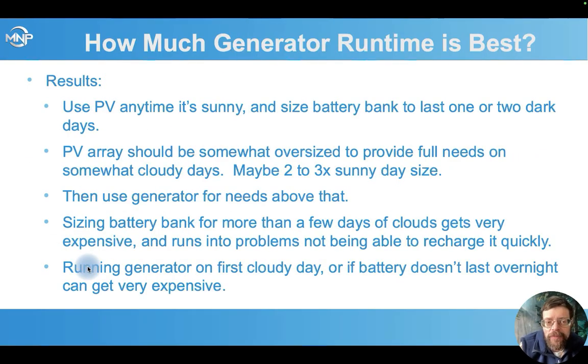What we generally come up with is that we want to use PV anytime it's sunny and size the battery to last at least 1 or 2 dark days. And we also want to oversize that PV array somewhat to provide the full needs on somewhat cloudy days, probably 2 to 3 times the sunny day size. This can vary a lot depending on your particular climate. And then after that, we use the generator.